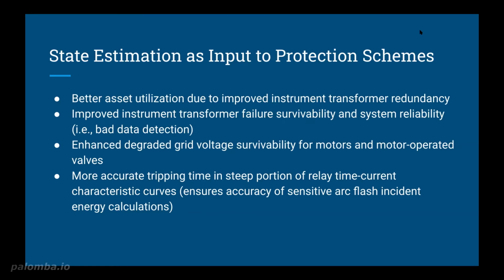A relay subject to input noise, or as seen by the relay, small change in arcing current, say, can cause a large change in arc flash incident energy for protective devices operating in the steep portion of their time current characteristic curves. This is because arc flash incident energy magnitude is affected greatly by arcing duration in addition to arcing current magnitude. So the largest fault current does not necessarily result in the greatest possible arc flash hazard. Therefore, noise could cause arc flash calculations to be inaccurate, and therefore the personal protective equipment selected for the job could be non-conservative.